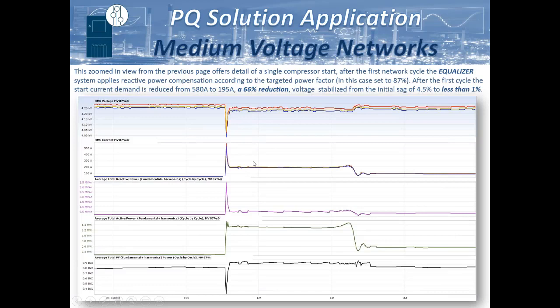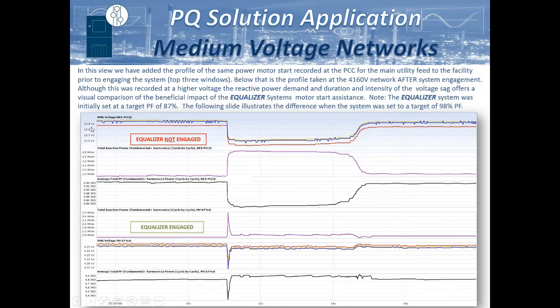So when we initially started, the client is an old utility guy and said, we'll just set the target at 87% power factor. So we did that as he requested and took some data, and then I told him to go ahead and set it up to 98%, leave it overnight, come back, and pull the data, because he was just leaving things on the table. We actually metered upstream of that location at the same time. I showed some of the baseline measurements before, as well as with the system engaged. You can see that even on the 13.8 line, there was a huge impact from those motor starts before the system was engaged. But after the system was engaged, it was a very steady state opportunity.